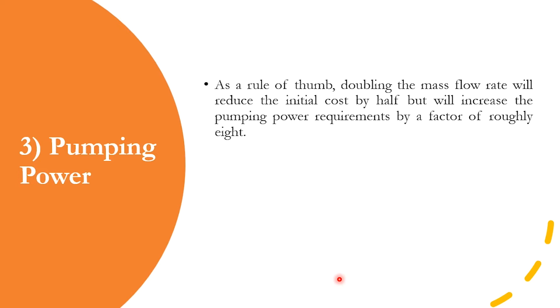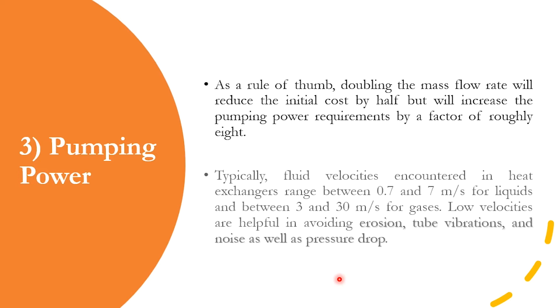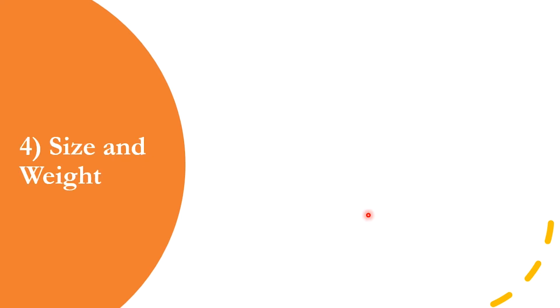You need to find a trade-off between how much reduction in flow rate you can afford and how much increase in pumping power you can afford. Typically, fluid velocities in heat exchangers range between 0.7 to 7 m/s for liquids and 3 to 30 m/s for gases. Low velocities are usually preferred as they help avoid erosion, vibration, noise, and high pressure drop.